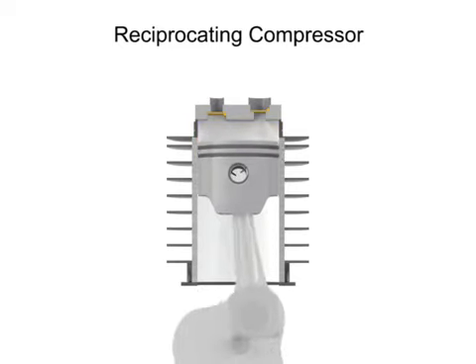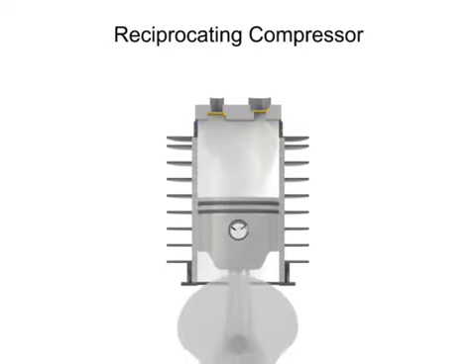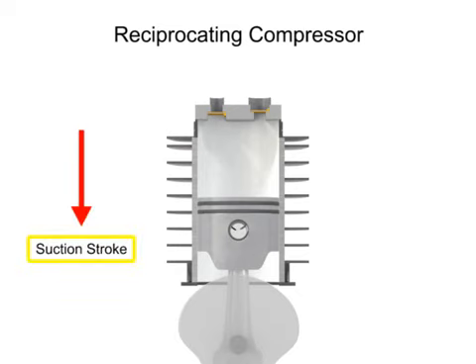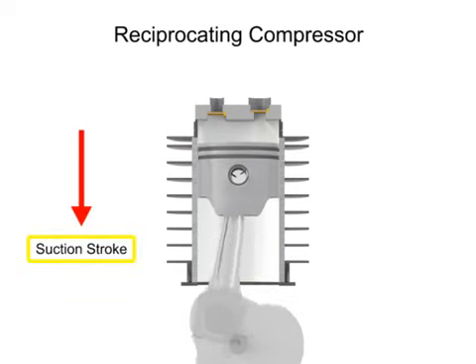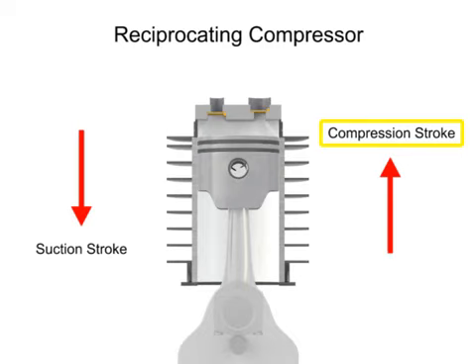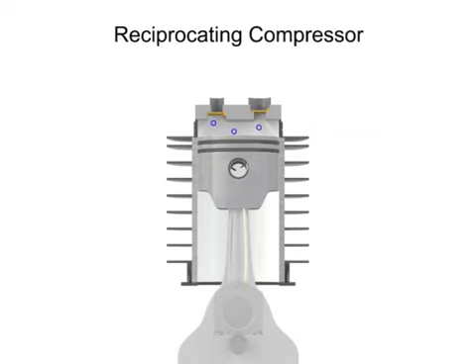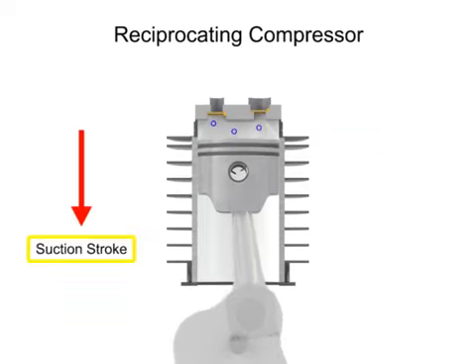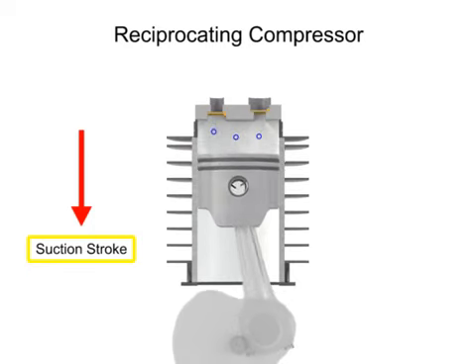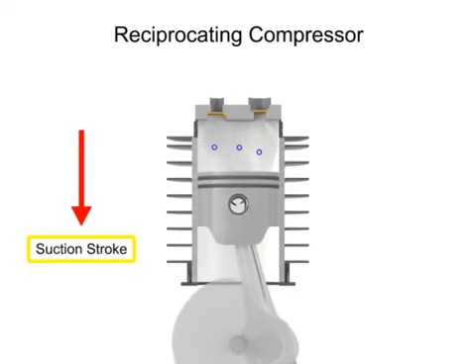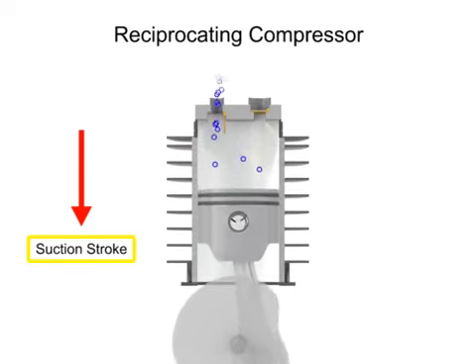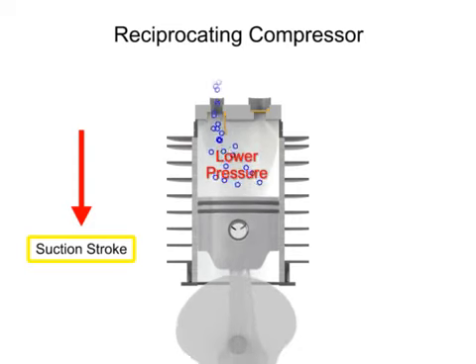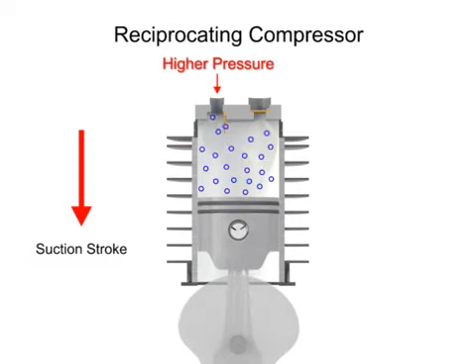The downward stroke of the piston is called the suction stroke, and the upward stroke is called the compression stroke. As the piston moves downward on its suction stroke, the volume increases within the cylinder. As the volume increases, the pressure within the cylinder becomes lower than the inlet air pressure, allowing the higher pressure outside air to push open the inlet valve and allow more air into the cylinder.